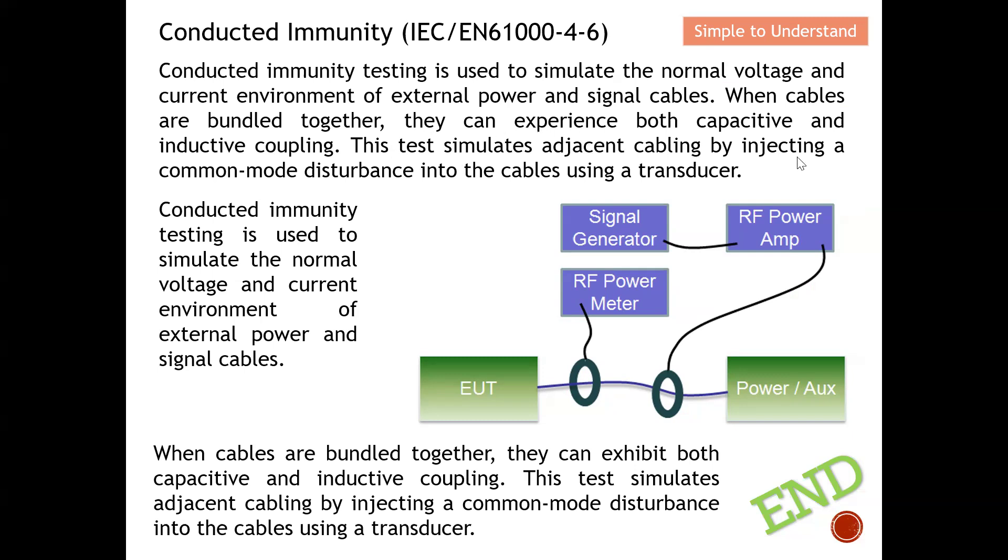This testing simulates adjacent cabling by injecting a common mode disturbance into the cable using a transducer. You send some signal that couples onto the cable and travels toward your device to see whether it can still function normally, or at least in some cases, you allow your device to fail but it must be able to reset on its own. We can inject disturbance through this coil and couple it over to the cable.